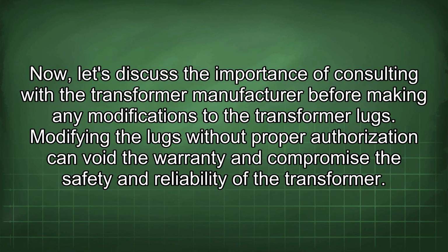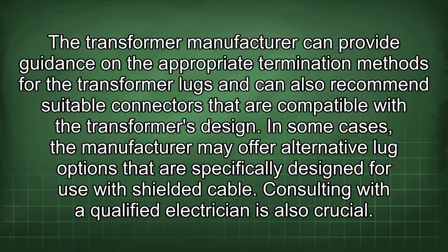Now, let's discuss the importance of consulting with the transformer manufacturer before making any modifications to the transformer lugs. Modifying the lugs without proper authorization can void the warranty and compromise the safety and reliability of the transformer. The transformer manufacturer can provide guidance on the appropriate termination methods for the transformer lugs and can also recommend suitable connectors that are compatible with the transformer's design. In some cases, the manufacturer may offer alternative lug options that are specifically designed for use with shielded cable.